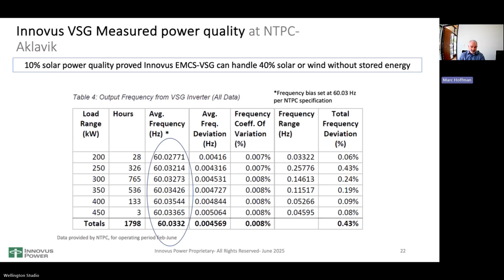For the engineers on the call worried about power quality, regardless of load, we are dead nuts at 60 hertz. It reads 60.03 because they wanted a slight bias when we set it up, intentionally. But you can see how tight the power quality is, regardless of where the community is in its load profile. Next.